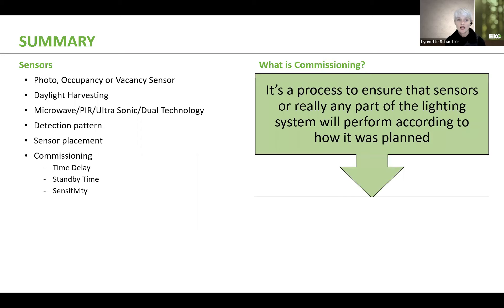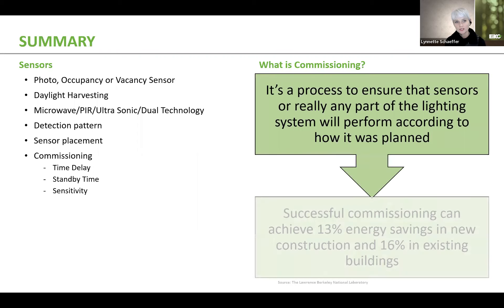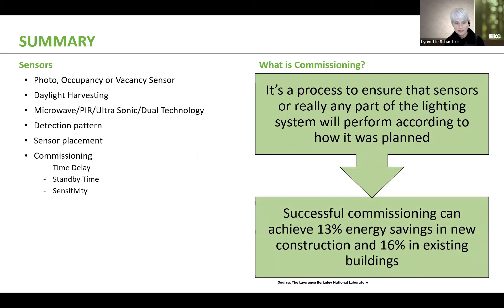Commissioning is a process that ensures the sensors will perform according to how it was planned. This is when you set things like time delay, standby time, sensitivity. And it's very interesting, but there was a little study that was done by Lawrence National Laboratory that says successful commissioning can achieve 13% energy savings in new construction and 16% in existing buildings. So you need to make sure you take the time to do the commissioning.